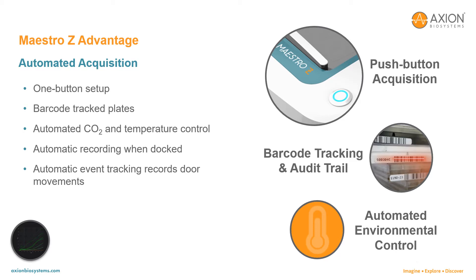Data acquisition starts automatically as soon as the plate is docked, and all 96 wells are simultaneously recorded in real time until the plate is removed. You can also input a custom gas mix into the chamber in the Maestro Z in order to reproduce the oxygen levels observed in in vivo inflammatory or cancerous conditions.